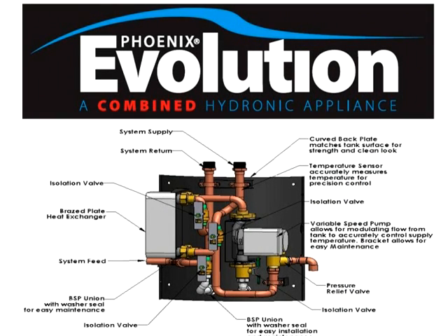A little closer picture of what we have here is the braze plate heat exchanger. Here is the variable speed circulator that's extracting heat from the tank, from the top of the tank, and then putting the flow coming out of the heat exchanger back into the middle of the tank. You can see all the isolation valves, and you can't really see the pressure relief valve very easily here.